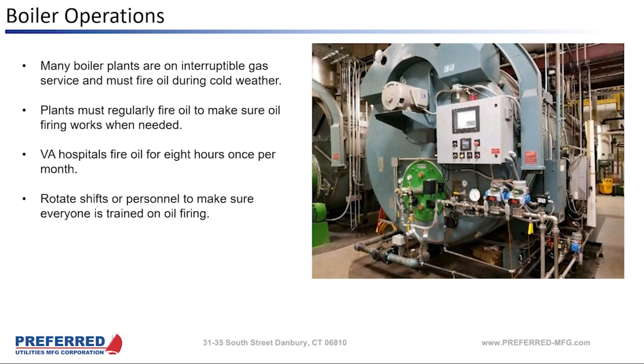So we've talked mostly about gensets so far. I want to talk a little bit about boilers. A lot of boiler customers are on interruptible gas service, and they'll be notified they've got to switch over to oil in cold weather, so we can save the gas for the homes that can't switch over. And here in the southeast, nobody has oil fired anything in their homes. All of our heat is either gas or electric. So the number one thing I run into when these plants switch over to oil is the operators don't have enough experience firing oil, and they don't really know how to do it.